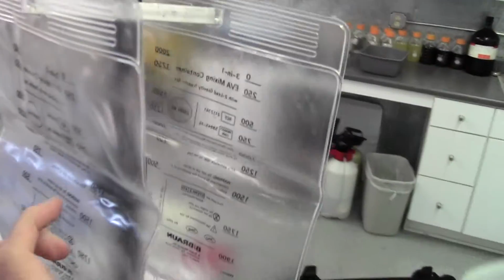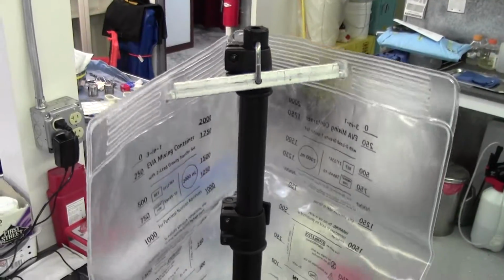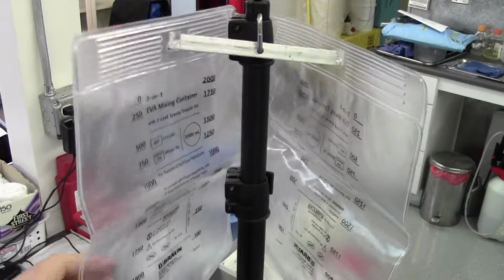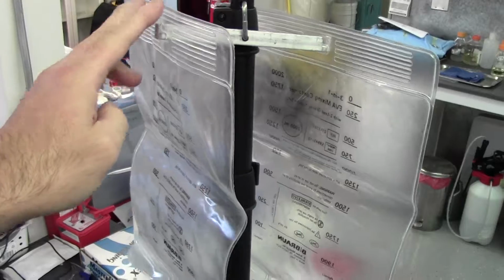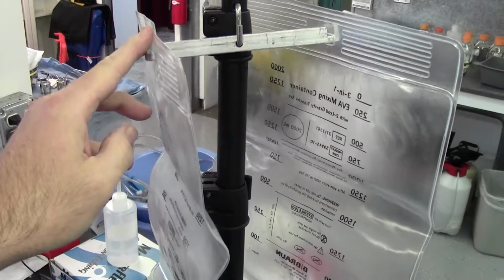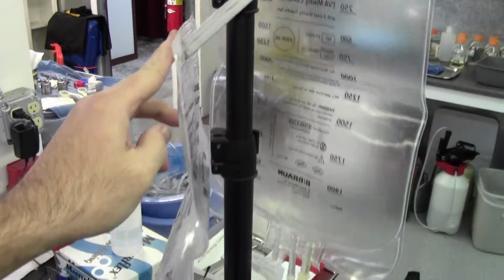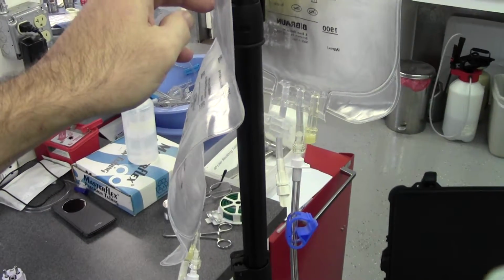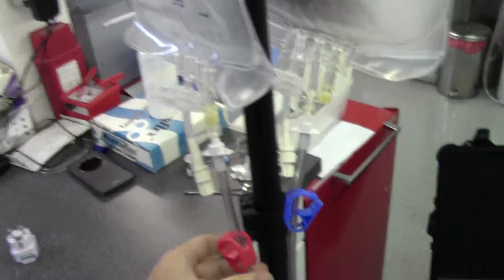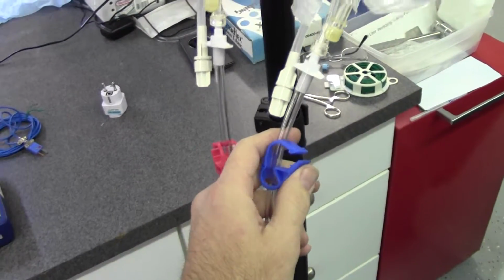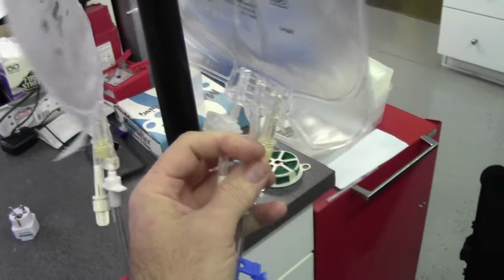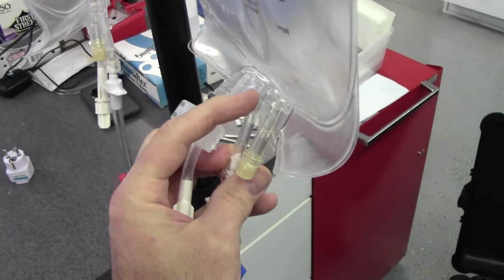Okay, you can see two bladders are hanging here. This is a teeter-totter. As the emptier bag travels upwards, it will rise in pressure and provide more flow, so it's sort of a smoothing of the two-step ramps together. When you're changing bags, you'll wait until the perfusate reaches about this level here.